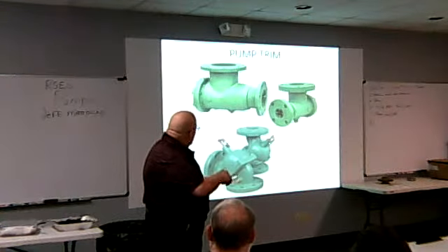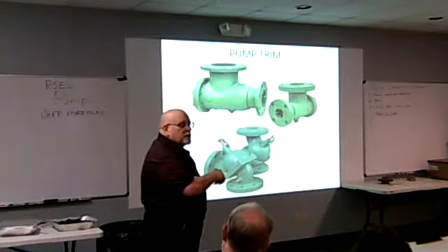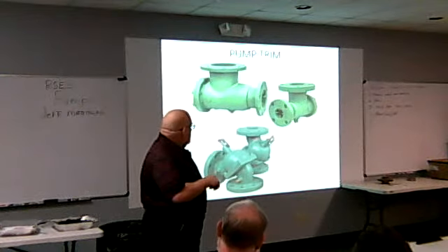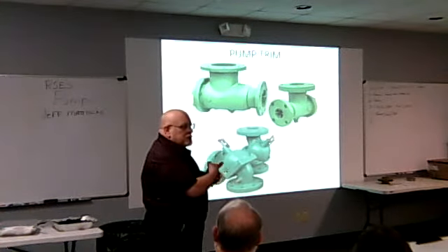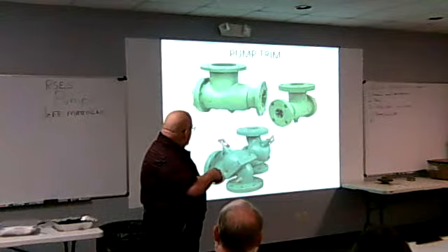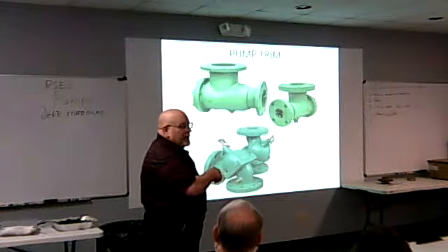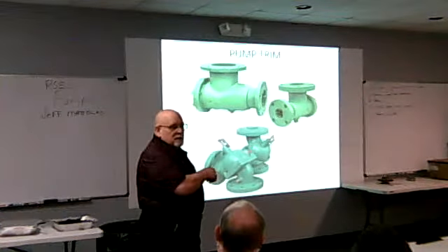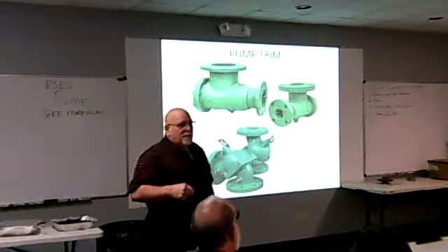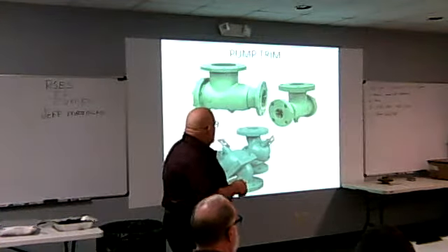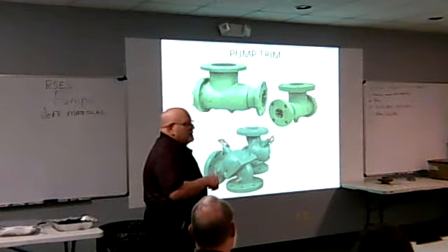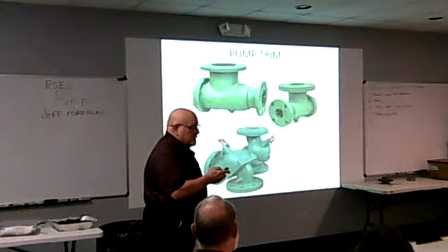You've got to remember where you had it set. There's a scale here. You can mark the scale. But when you turn it all the way down, it'll go to shut off, or you can take it back to your balance. There's a little indicator here. You can mark, put the indicator where your balance position is. And then you can just reopen the valve right to that balance position. We make these in 150 pound and 250 PSI pressure valves.